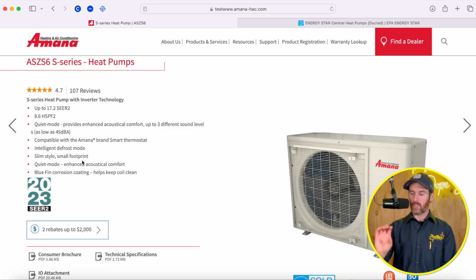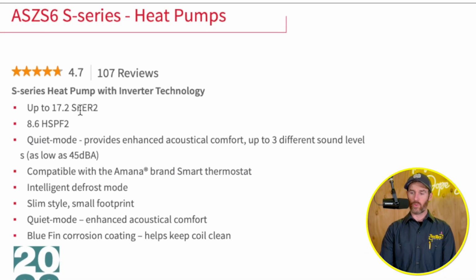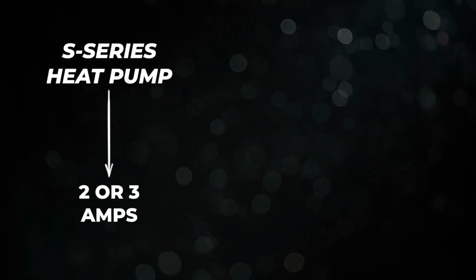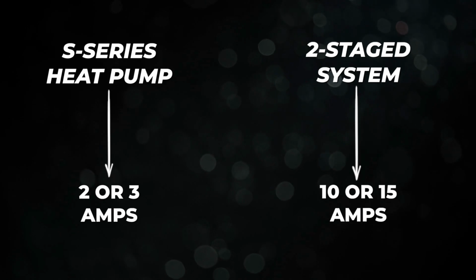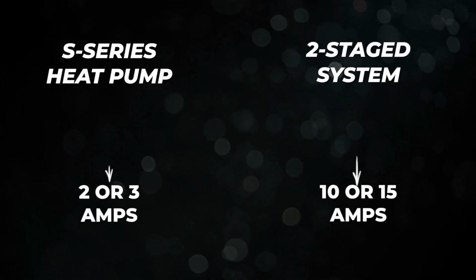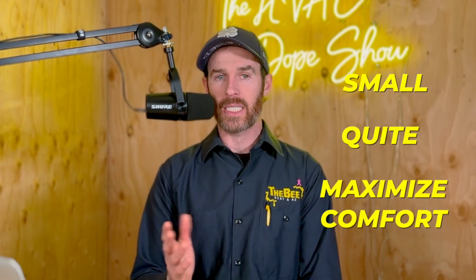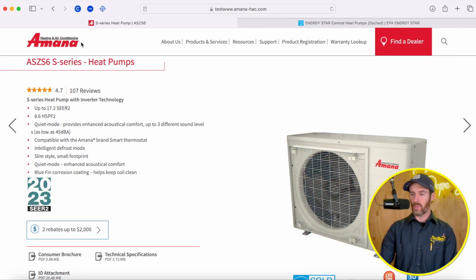Now, the way that these systems make that higher efficiency, even though the SEER rating is basically identical with the two-stage system, is that these systems ramp up and down along a continuum. And so when this first kicks on, it might pull 2 or 3 amps compared to that two-stage system I showed you is still probably pulling 10 amps or maybe 15 amps depending on the tonnage. So it's still going to be much more efficient when it first kicks on. And that's where these systems really shine, is that they're small, they're quiet, and they maximize comfort because they ramp up and down. And so you get less hot spots and cold spots in your house because you get longer run times and therefore more air circulation. So this type of system is one of our best sellers.